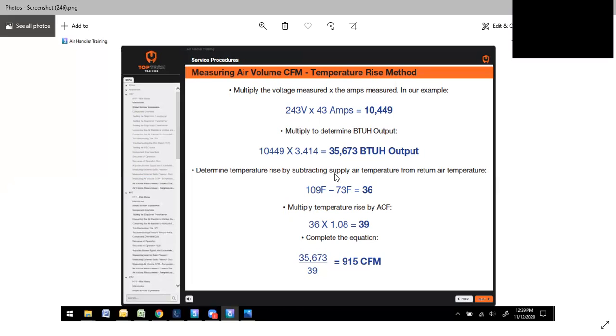Determine the temperature rise by subtracting the supply air temperature from the return air temperature. So you have 109 minus 73, which gives you 36. Multiply the temperature rise by your constant, 36 times 1.08 equals 39. Divide that, and you know you're operating at 915 CFM. If that's where you need to be, then you're perfectly fine. If you're not, then you need to make some provisions to adjust that.